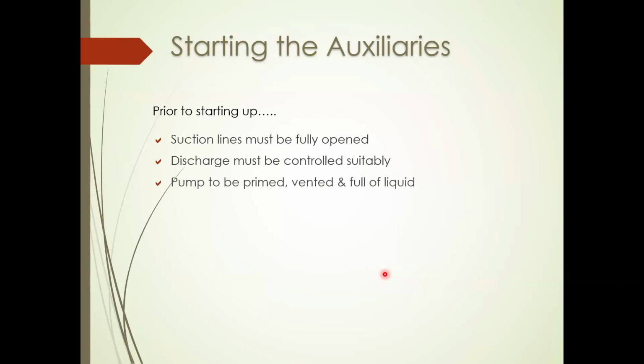And most importantly, if it is a centrifugal pump, you have to prime the pump, vent the line, and fill the line full of liquid. Otherwise, if air pockets remain when you start the pump, your line will get hammered and sometimes it will break. And then, of course, you have to protect the pump impellers from eroding. So the pump priming is quite important.